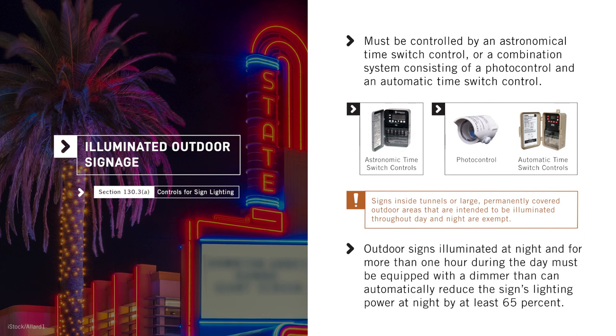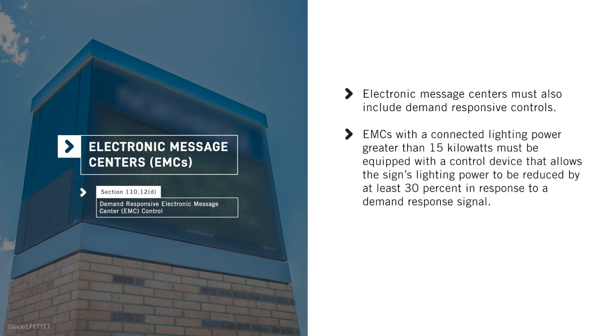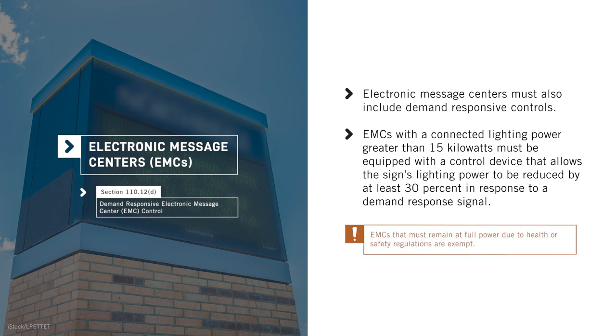In addition, outdoor signs that are illuminated at night and for more than one hour during the day must be equipped with a dimmer that can automatically reduce the sign's lighting power at night by at least 65%. A specific type of outdoor sign called an electronic message center, or EMC, must also include demand responsive controls. EMCs with a connected lighting power greater than 15 kilowatts must be equipped with a control device that allows the sign's lighting power to be reduced by at least 30% in response to a demand response signal. EMCs that must remain at full power due to health or safety regulations are exempt.